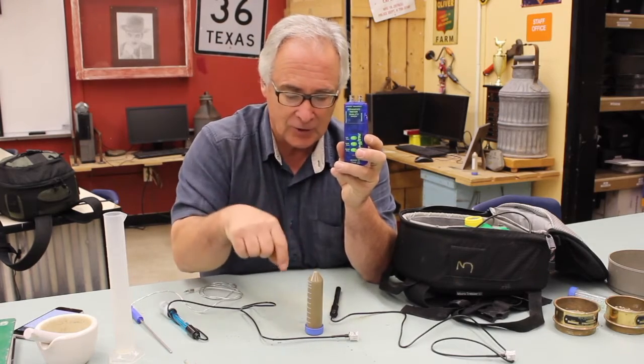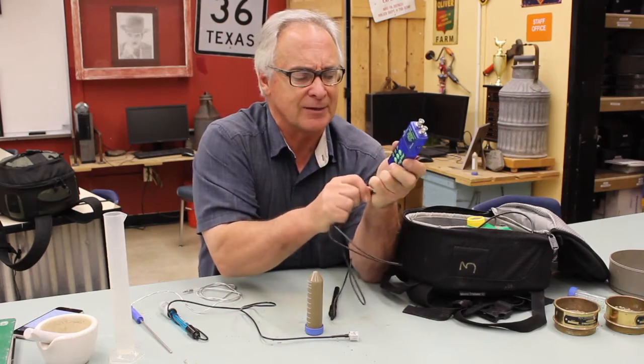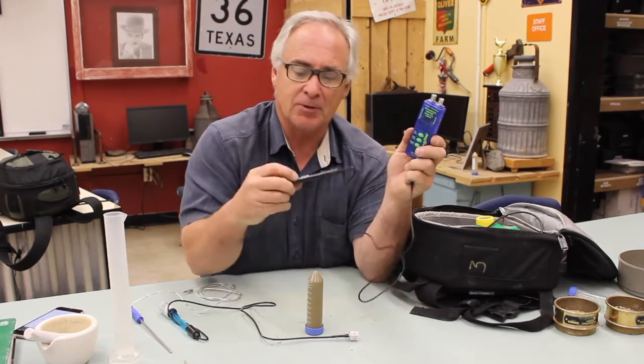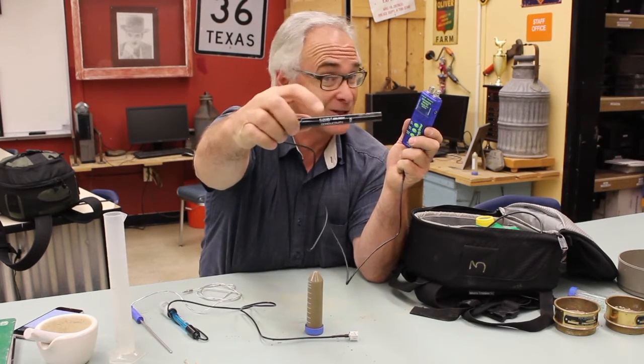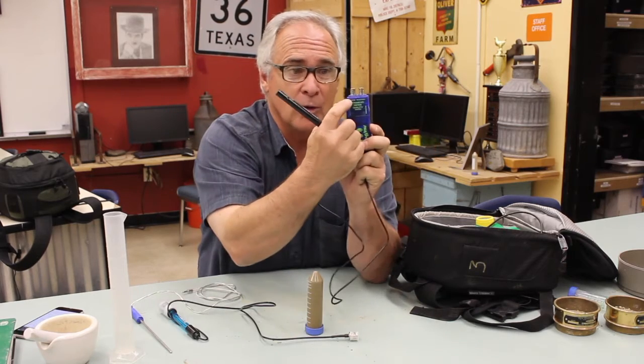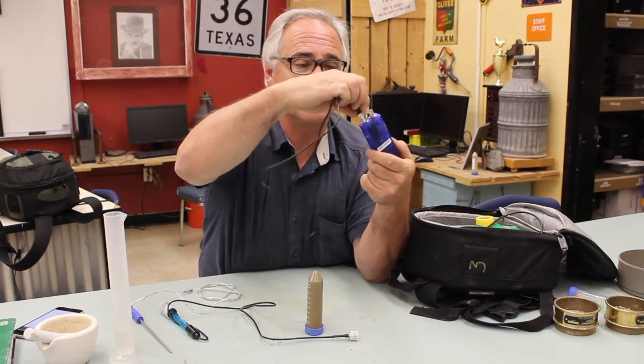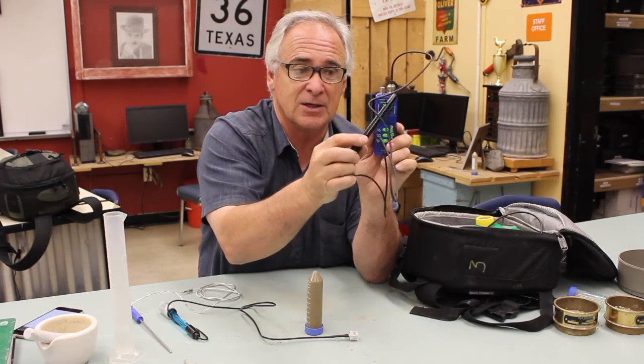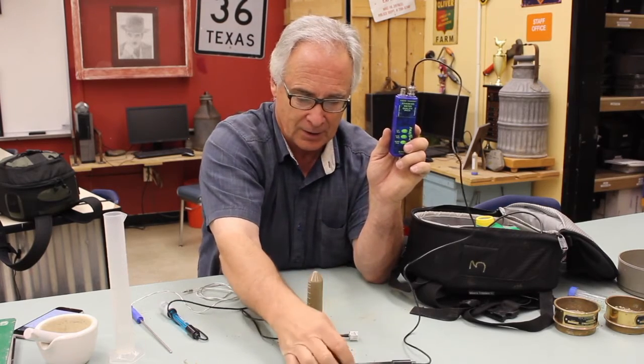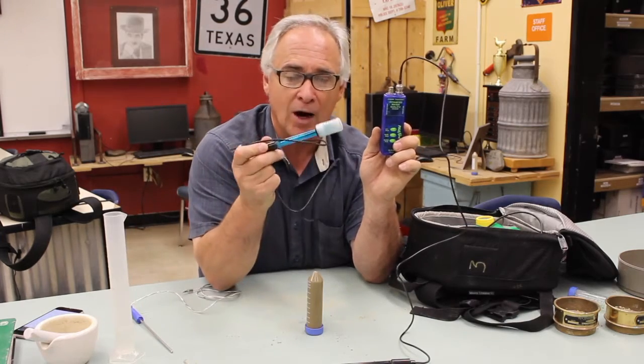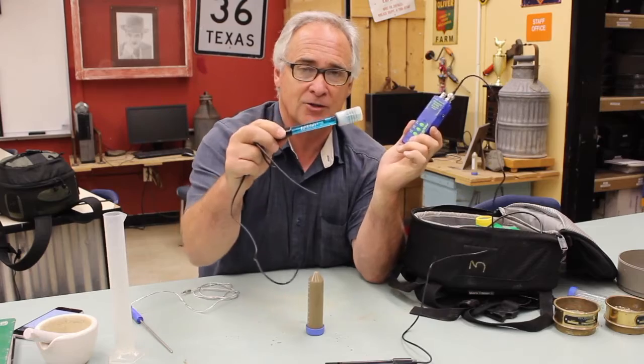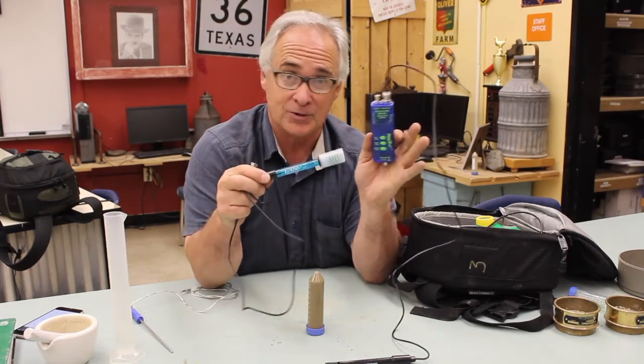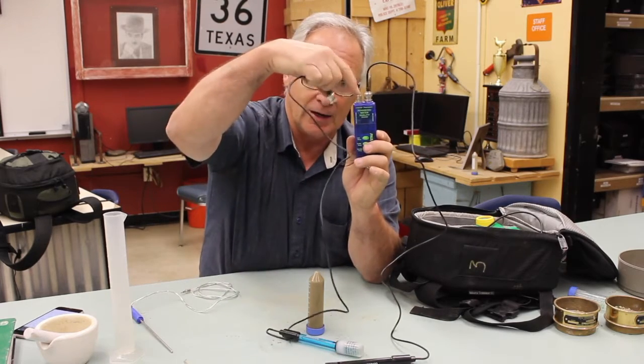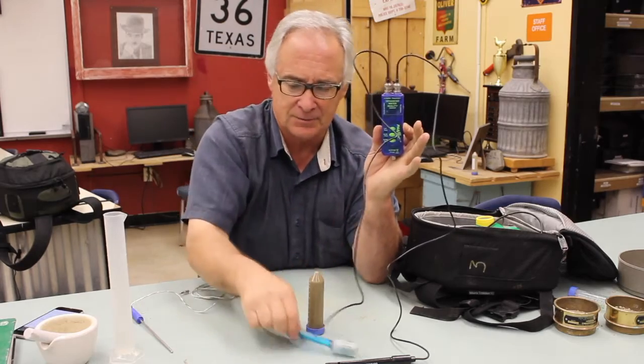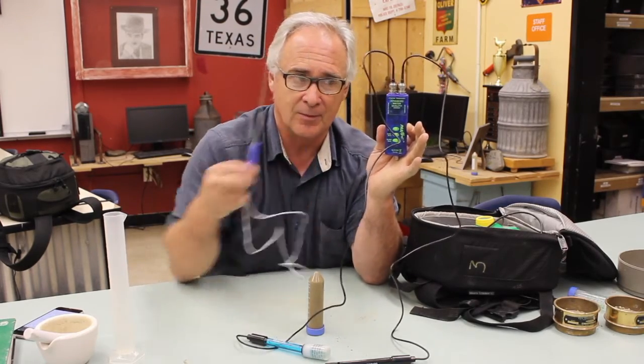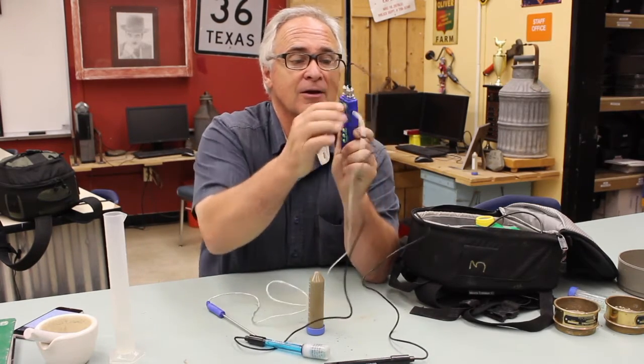In order to make all this work, we first of all have to make sure we connect everything. So this is the sensor, this is the probe. This probe is called the conductivity sensor. It says so right on the probe. And you match it with whatever it's labeled here. Since it's labeled conductivity here, this is the EC reading, or the electric conductivity part of our sample. And then we're also going to get the aquatic pH. It's this one right here. It says pH on it, but it's the blue, which reminds me of water, which means that's the aquatic variety. So that goes right on this coax connector. And then the other thing is a stainless steel temperature probe, and that will go right over here on the side where it says temperature.